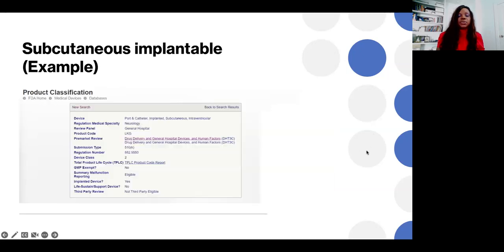So next slide, please. I used the LKG as an example. I clicked on LKG from the previous screen, and this is what comes up. It's telling me that this is a catheter implanted subcutaneous intraventricular device. The specialty is neurology. The product code is LKG, but it's also telling me that the submission type is a 510K. The device is class 2, and so on and so forth. So the product code really is laying out the regulatory framework for your product. It's important that you check them to see which one is most applicable for your device.